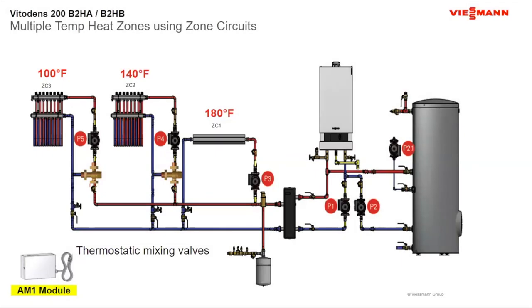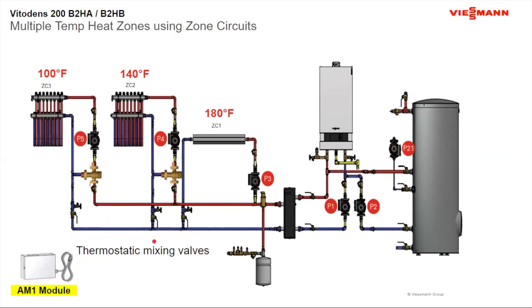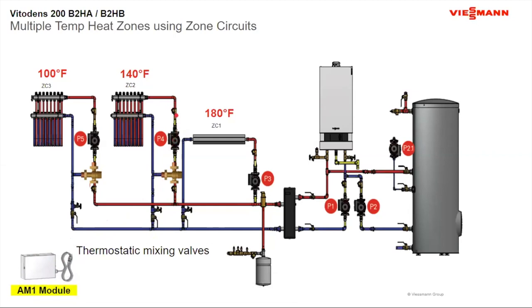So now you can see three different temperatures going right to the boiler: one high temp on ZC1, one medium temp on ZC2, and one low temp on ZC3. This example uses thermostatic mixing valves. If you use our mixing valves, they have a control box similar to the AM1 module that plugs into the wall. It controls the pump, has a strap-on sensor to check mixed outlet temperatures, and constantly modulates to maintain the proper temperature.